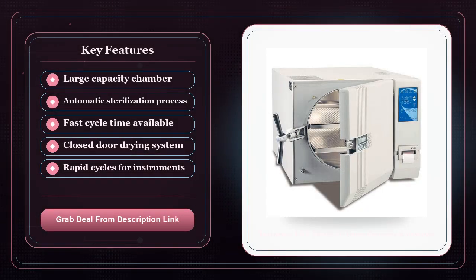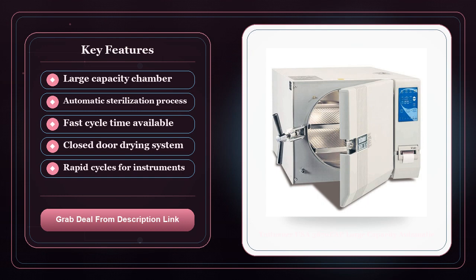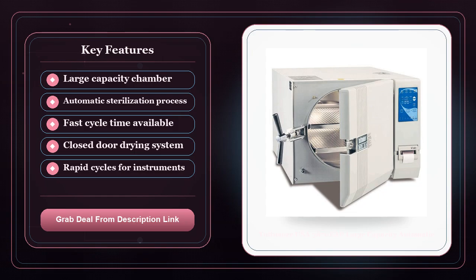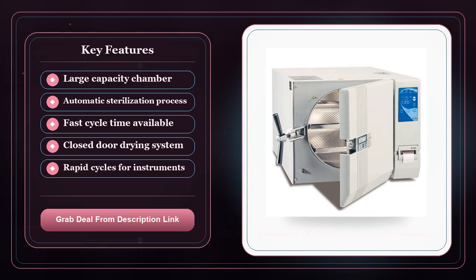First off, the chamber. At 22 gallons, roughly 85 liters, it's big enough to take a full set of dental instruments, a batch of surgical trays, or a stack of lab glassware in one go. The internal dimensions of 15 by 30 inches mean you can lay out standard trays flat without crowding, which translates to fewer loads per day. In a practice that sees a steady flow of patients, that can shave off the minutes you'd otherwise spend loading and unloading a smaller unit. I've heard from colleagues that the full chamber approach reduces overall turnaround time, not because the cycles are faster, but because you're moving more items per cycle.